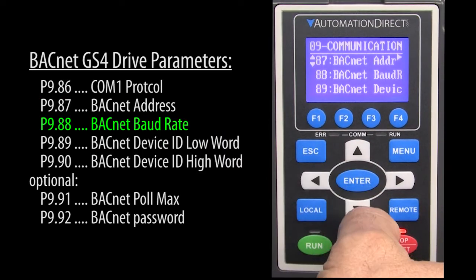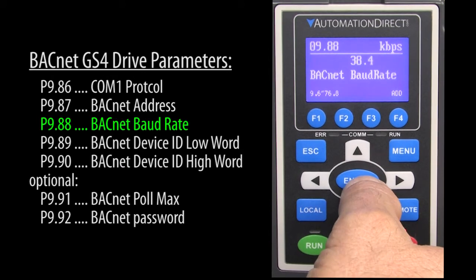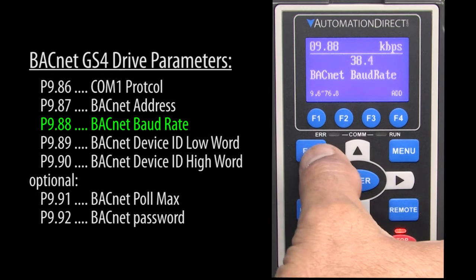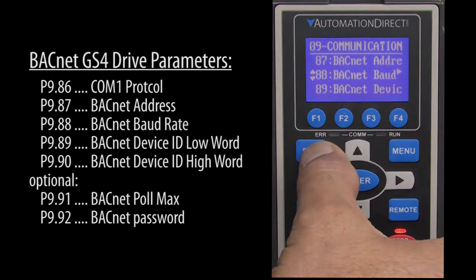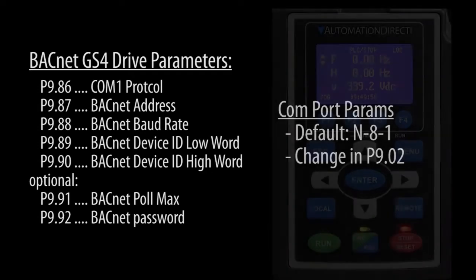Make sure the baud rate is what you need. Our USB to 485 converter we'll be using is set to 38.4k baud, so this is correct. The COM port parameter defaults to N81, but you can change that in parameter 9.02 if you need to.